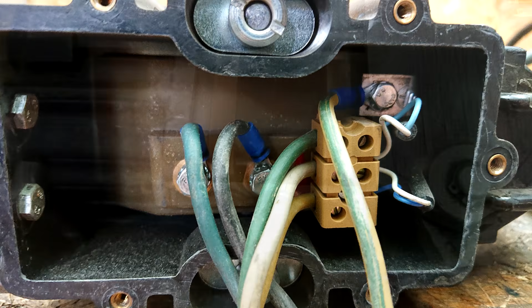The transformer is potted, and only 2 wires lead to its primary - the black and the blue one. This tells us that we don't actually need 3 phases. It's a single-phase transformer, but it's supposed to be connected between 2 phases of a 3-phase power outlet.